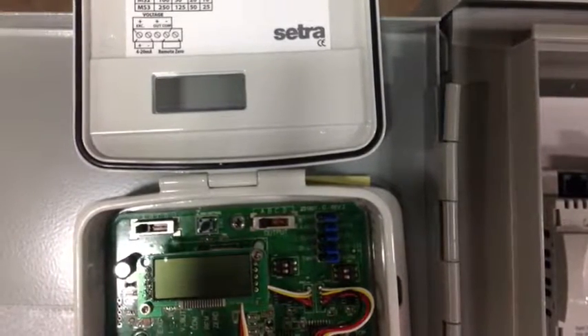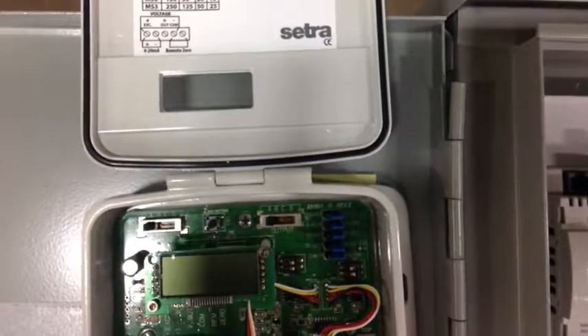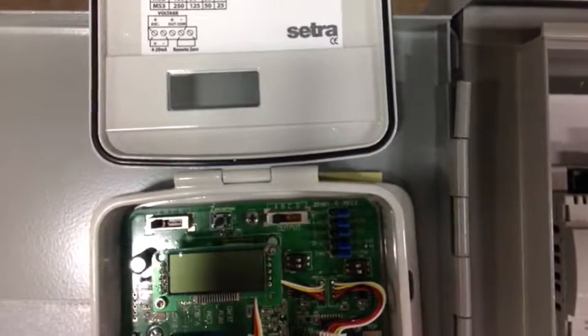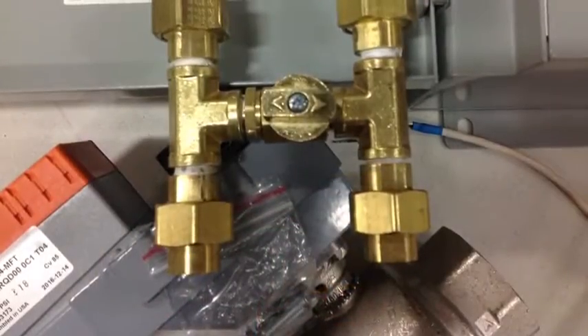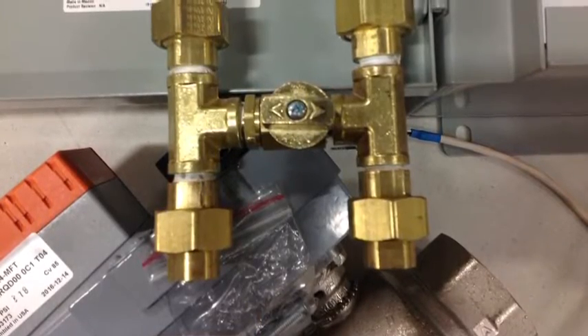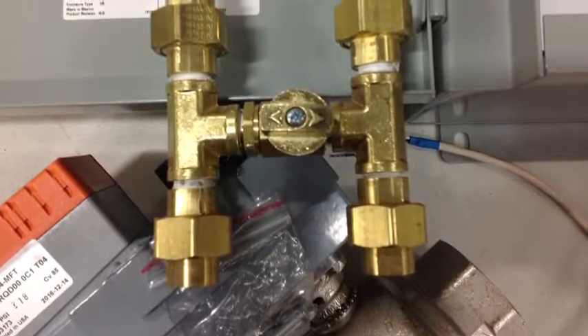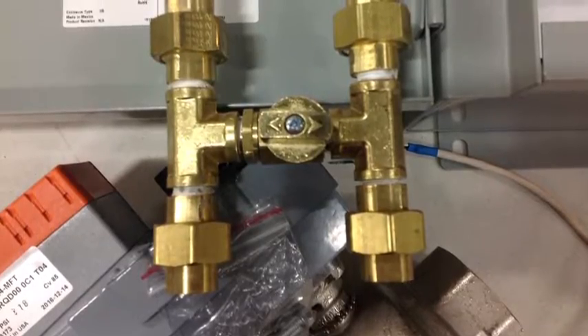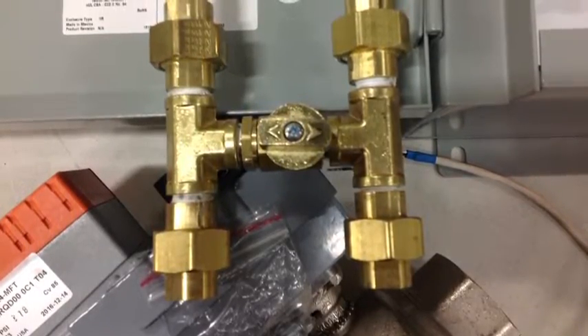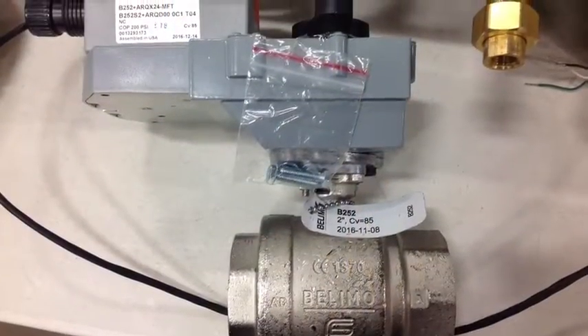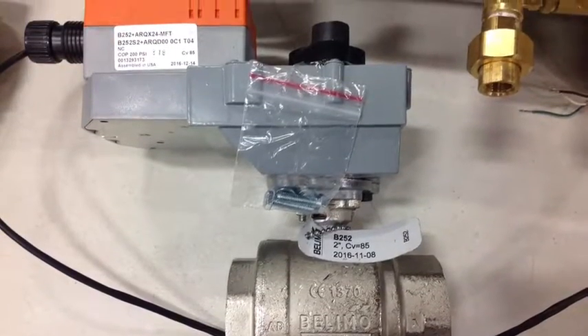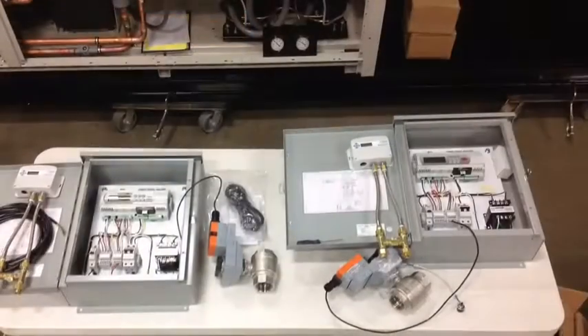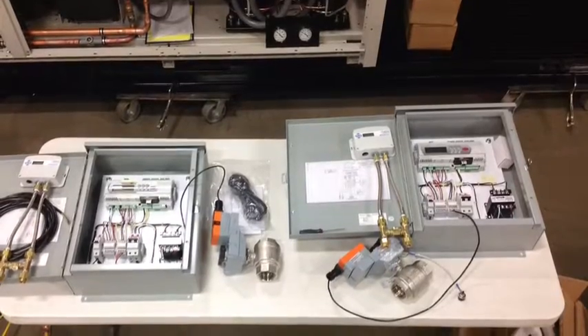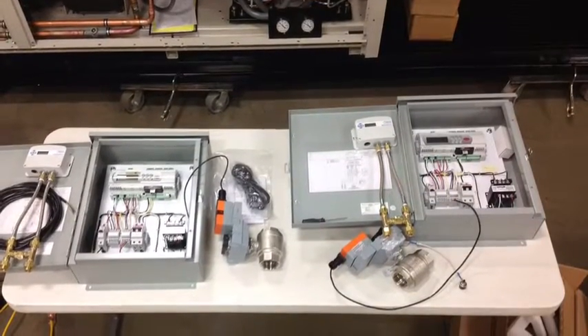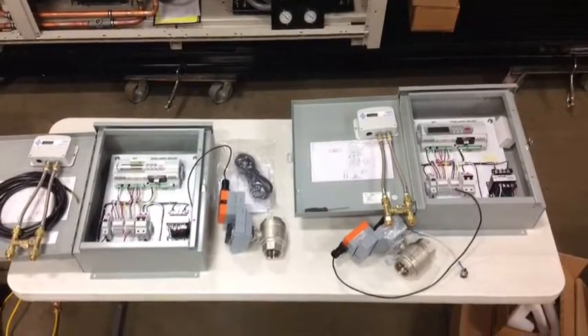The differential pressure in the loop will need to be determined and estimated before committing. In addition, this valve assembly ships with the differential pressure transducer, allowing pressure equalization and use of the zeroing feature to calibrate the differential pressure transducer. Again, this 3-piece assembly, 1 for each floor, the end-of-loop bypass, the control cabinet, and the differential pressure transducer.